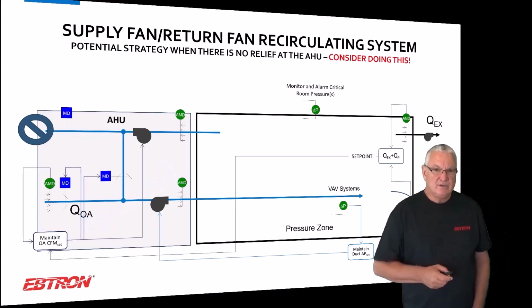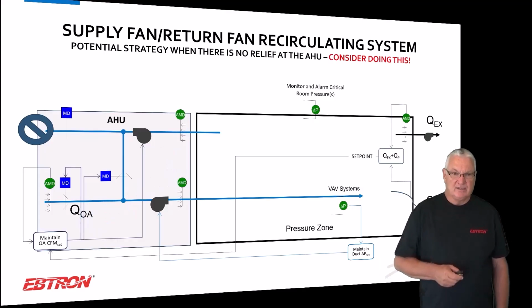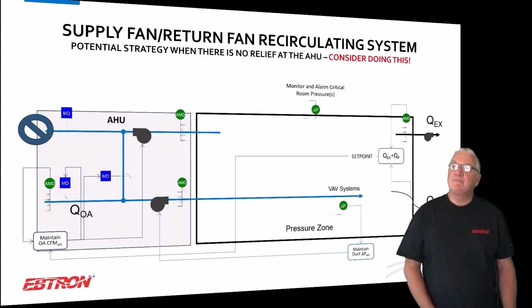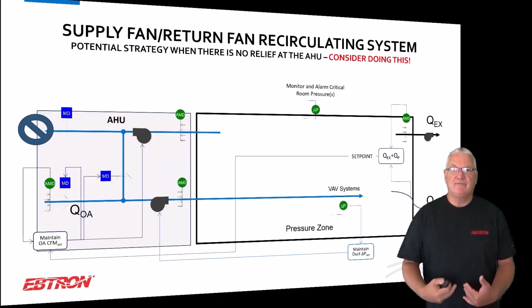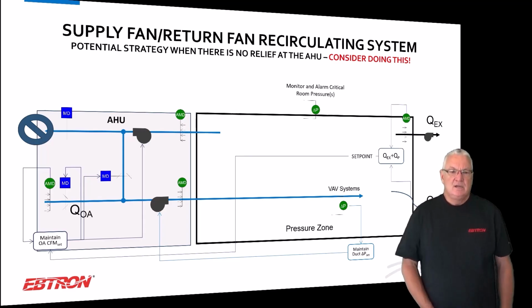What you want to do is what we're going to show you here. This is the method we do. It doesn't mean you have to do this. The method that we like, so we say consider doing this, is when there's a return fan and there's no relief, we make the return fan our friend. We use it as part of our strategy to maintain outside air.